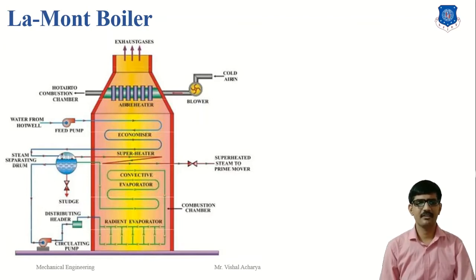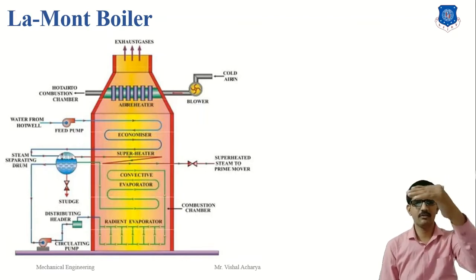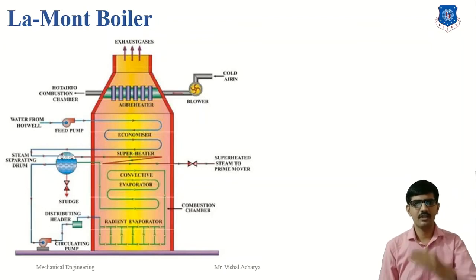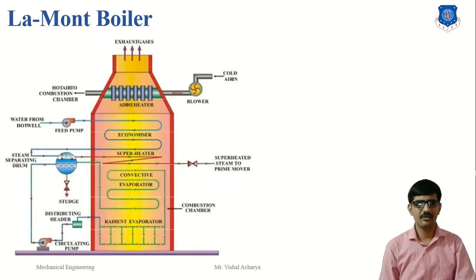The steam separating drum separates the steam from the water. Steam gets collected at the upper portion and water at the lower portion of the drum — meaning the upper part is filled with steam and the lower part is filled with water. The circulating pump is driven by the turbine. It circulates the water from the steam separating drum to the small diameter tubes of the radiant evaporator and convective evaporator, and back to the steam separating drum. The radiant evaporator increases the temperature of water by radiation.